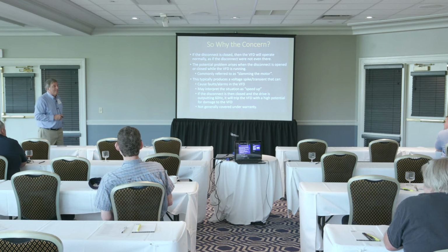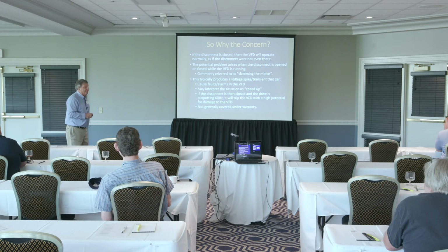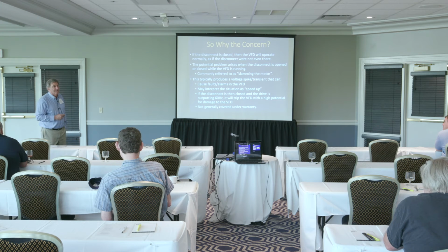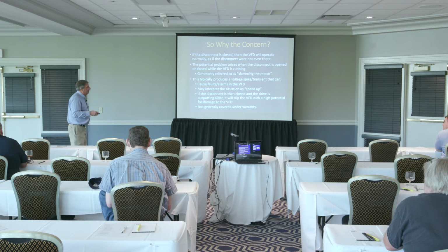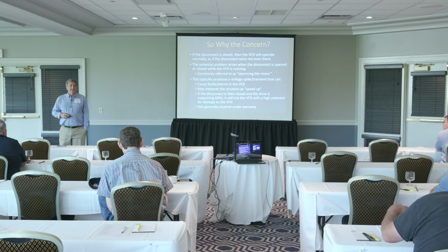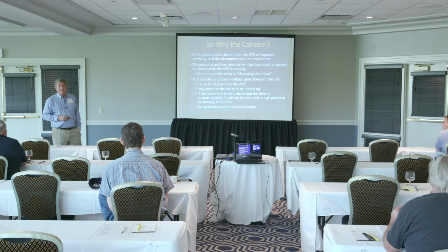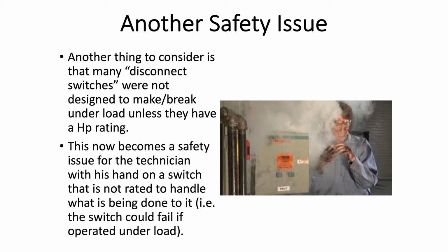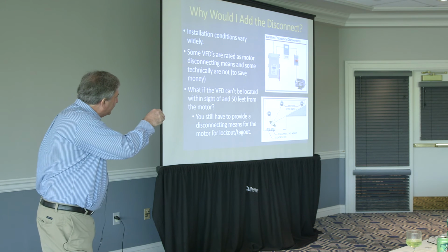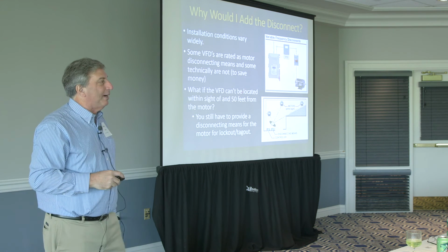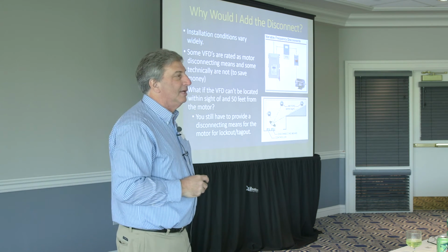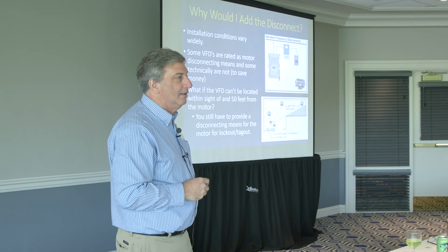That type of high potential damage. And if you're standing near there, the shrapnel and the concussive blow can be pretty bad. Oh, and by the way, the manufacturers say that's not covered under general warranty. That's on you. Another thing to consider is that many disconnect switches were not designed to make or break under load unless they have a horsepower rating. So I see people that put that disconnect in there and it's not a horsepower rated disconnect for a motor. It's an amp rated disconnect only.